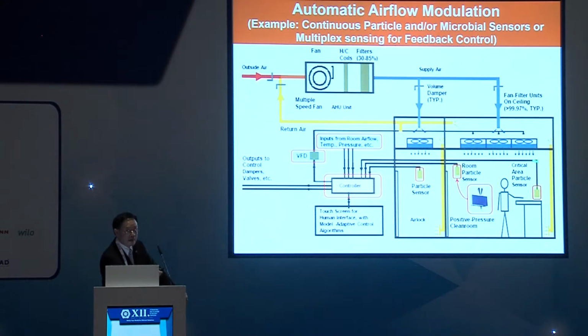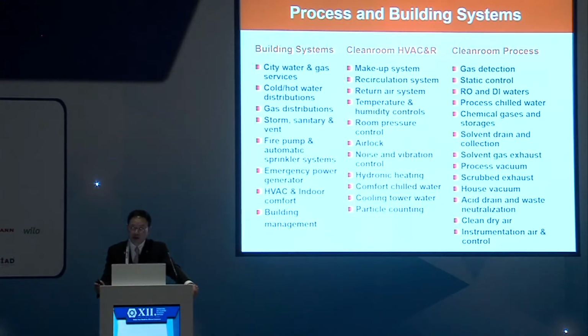During the evening or weekend, once the room is unoccupied, this particle sensor tells you my room is very clean, I'm maybe ISO 4 or ISO 3, much cleaner. If you want to maintain ISO 5, you have a chance to reduce the airflow. How much to reduce? The particle sensors will tell you. So this particle sensor is pretty much like the thermostats that we're using today. A thermostat tells you the room temperature in real time. Particle sensors can tell you the real air cleanliness class in real time. Many years ago, this device was much more expensive, so it was not feasible. But now it has become more cost effective. So sometimes the design firm can help the owner reduce the energy consumption. This is part of your knowledge, this is part of your design consideration.